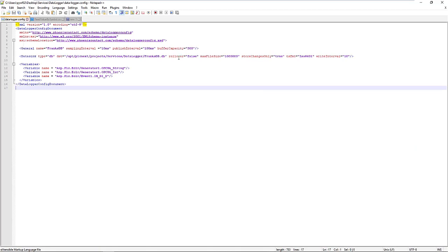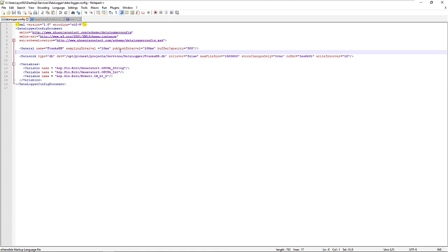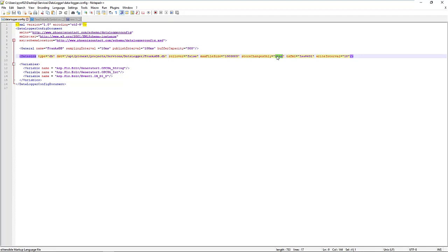And here we go. Most of the keys are, I guess, quite already familiar, so we can leave them behind. The most important one is the stored changes only flag, which is now changed to true. As soon as this flag is set, or this key is inserted in the configuration file, the data logger will only record changes of the configured variables.